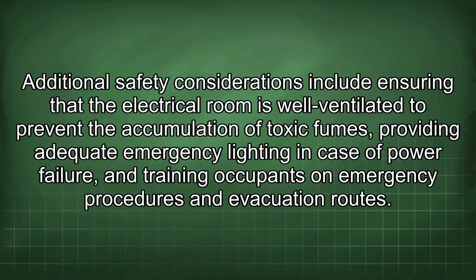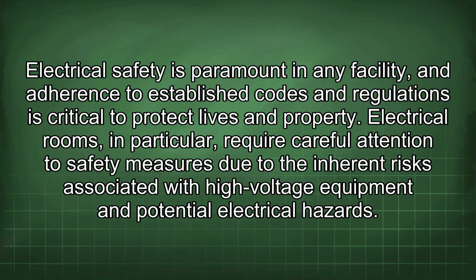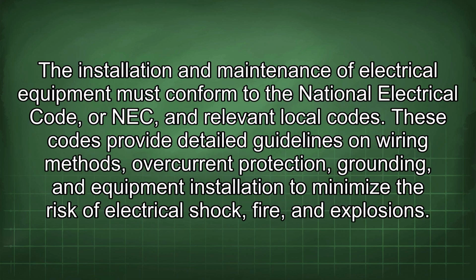Additional safety considerations include ensuring that the electrical room is well ventilated to prevent the accumulation of toxic fumes, providing adequate emergency lighting in case of power failure, and training occupants on emergency procedures and evacuation routes. Electrical safety is paramount in any facility, and adherence to established codes and regulations is critical to protect lives and property. Electrical rooms, in particular, require careful attention to safety measures due to the inherent risks associated with high-voltage equipment and potential electrical hazards. The installation and maintenance of electrical equipment must conform to the National Electrical Code, or NEC, and relevant local codes. These codes provide detailed guidelines on wiring methods, overcurrent protection, grounding, and equipment installation to minimize the risk of electrical shock, fire, and explosions.